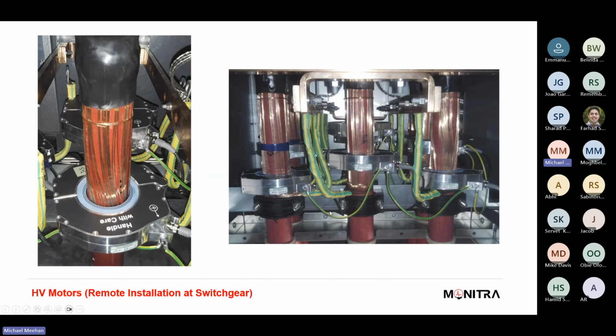In terms of what these installs look like, these are HFCTs on obviously the cable cores, and you can use this method obviously to detect the PD on a machine. This could be an at switchboard measurement solution. So we could measure PD, potentially, or we do measure PD from the switchboard to the machine.